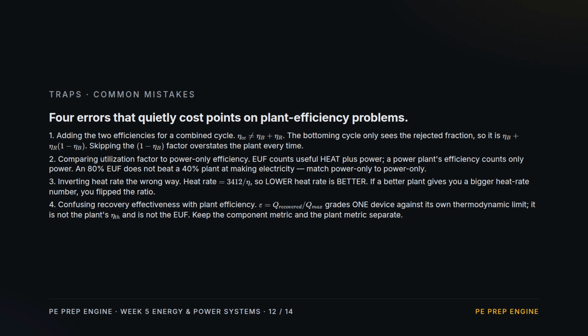Three. Inverting heat rate the wrong way. Heat rate is 3412 over efficiency, so lower is better. If a better plant gives you a bigger heat rate number, you flipped it. Four. Confusing recovery effectiveness with plant efficiency. Effectiveness grades one device against its own limit. It is not the plant efficiency and not the utilization factor. Keep component and plant metrics apart.